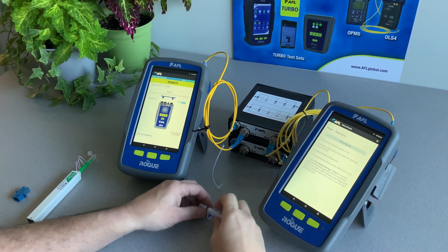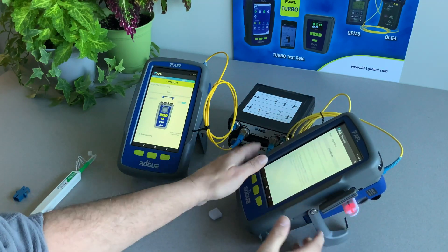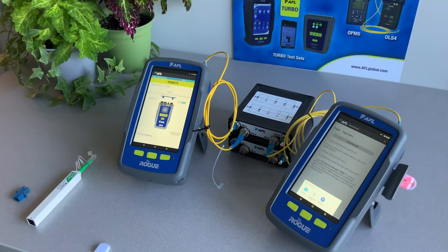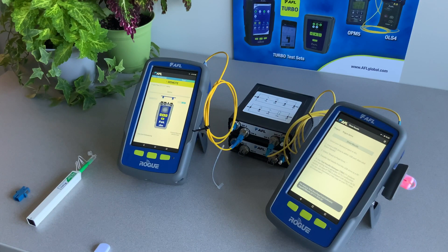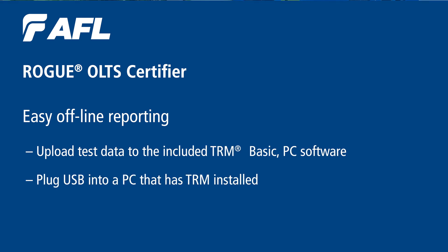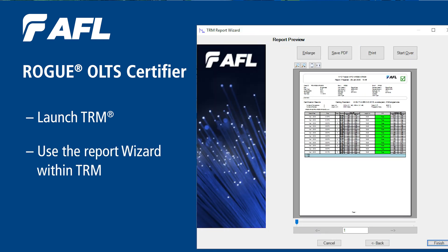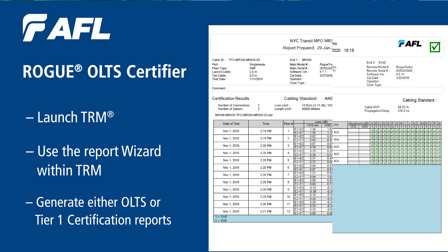Plug a USB drive into the unit. Tap Share Results and select Save to Flash Drive. Now you can take the USB and plug it into a PC that has TRM installed. Launch TRM and use the Report Wizard within TRM to generate either an OLTS or Tier 1 Certification Report.